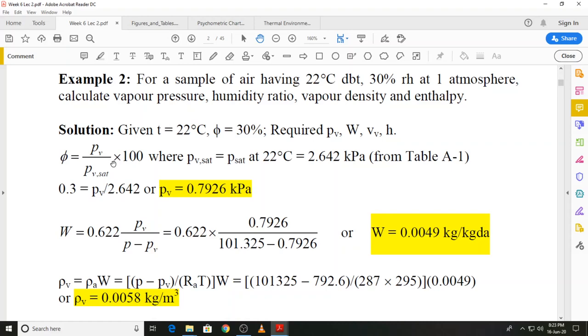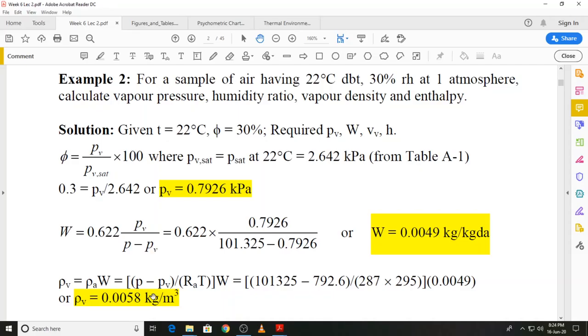The expression for relative humidity is φ = Pv / Pv_sat × 100%. φ is given as 30 percent. We first find Pv_sat from the given dry bulb temperature of 22°C using Table A1. At 22°C, the saturation pressure P_sat is 2.642 kilopascals. Substituting, we get the partial pressure of water vapor at 22°C dry bulb and 30% relative humidity, which comes out to be 0.7926 kilopascals.